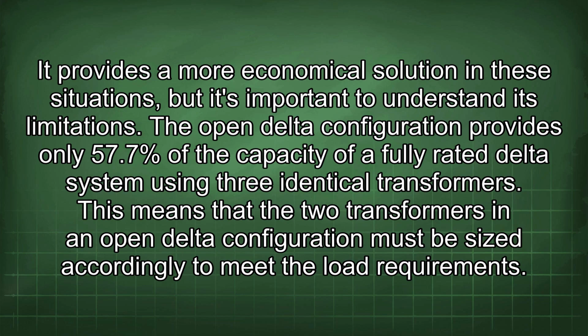It provides a more economical solution in these situations, but it's important to understand its limitations. The open delta configuration provides only 57.7% of the capacity of a fully rated delta system using 3 identical transformers. This means that the 2 transformers in an open delta configuration must be sized accordingly to meet the load requirements.